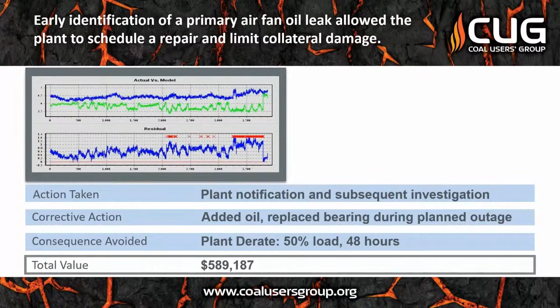The operator found that oil was leaking from the fan bearing and it was being drawn into the fan, creating an imbalance and causing increased vibration. The plant actually had a scheduled maintenance outage for the upcoming weekend, and they took that outage and made repairs to the fan at that time. And in our talks with the plant operations, it was agreed that if repairs hadn't been made, the fan would have likely tripped within a day or two after the startup of their maintenance outage. And the value that you see there is based on a 50% derate of the unit. However, I'll also share with you that the plant also let us know at that time that they had never in the history of the plant been able to survive basically an uncontrolled PA fan trip.